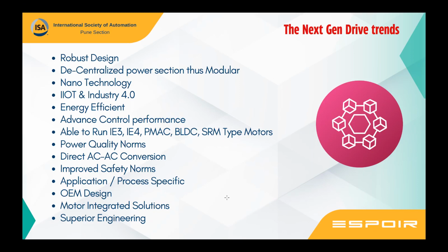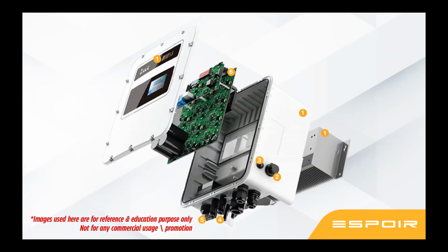Power quality norms are getting stringent. So the drives are also coming with a lot of options to cut down on that. Direct AC to AC conversion models have come, which will greatly reduce the harmonics related issues. Commercially, it is still not viable. Improved safety norms, application of process specific drives, OEM designs. Now, manufacturers started designing VFDs based on the applications and the customer demand. Motor integrated solutions, superior engineering. So this is what you saw. This is a superior engineering solution.